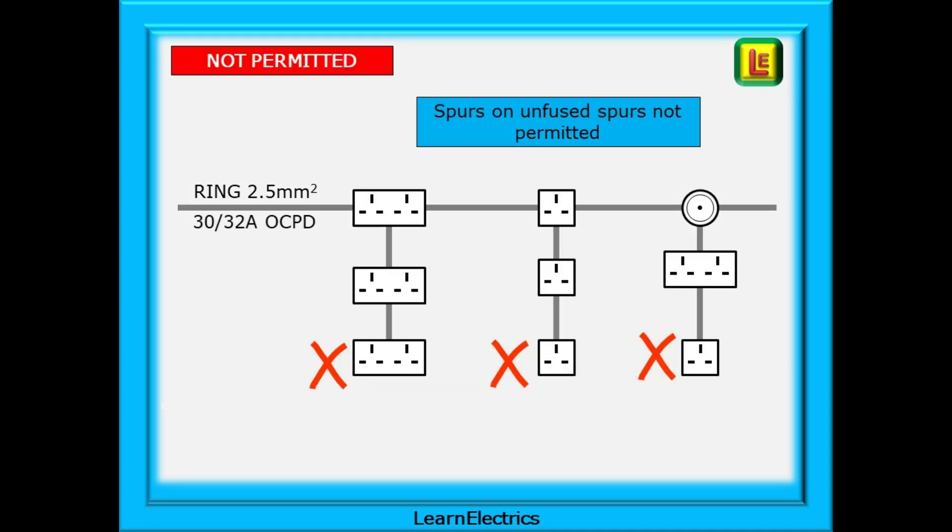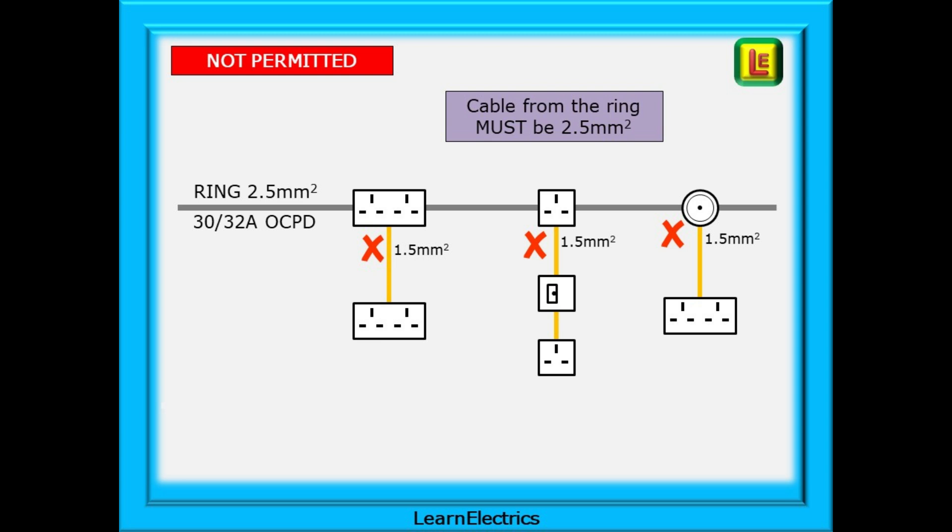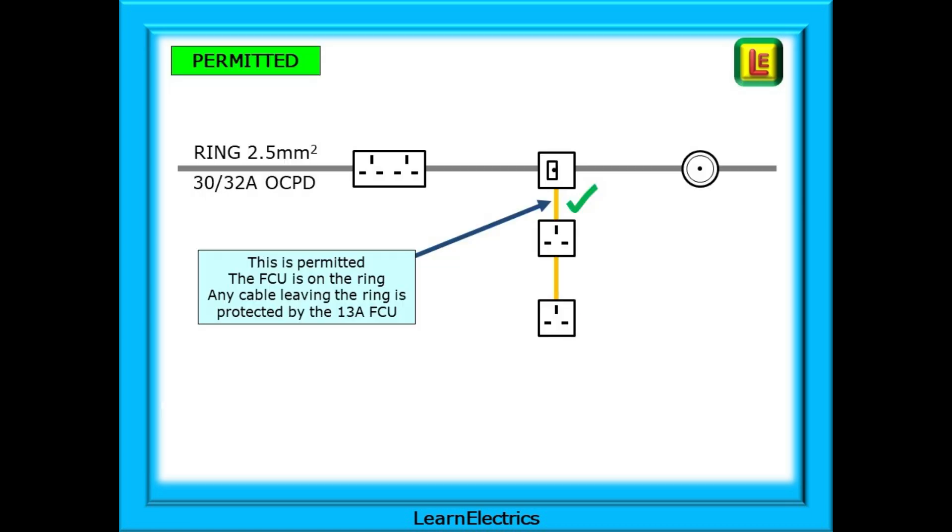So spurs on unfused spurs are just not permitted, and cables from the ring must be the same size as the ring conductors, in this case 2.5mm. Using smaller 1.5mm cable to come off the ring is not permitted in most cases. However, if there is a fused spur, in other words an FCU sitting on the ring, then we can come off the ring straight away with 1.5mm cable.